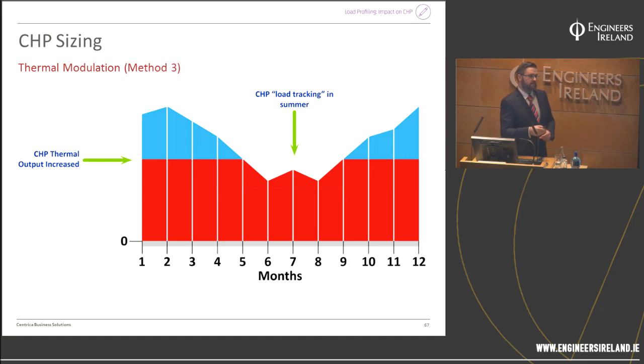Thermally, well electrically, it's 50%, it'll modulate electrically 50%. But for every 10% there, it equates to about 1 degree Celsius in your actual live temperatures. So if you think about that, that's only 5 degrees you've got to play with on a flow and return, before the engine starts to not be able to deal with the heat that it is feeding back from the site and then trying to feed out.